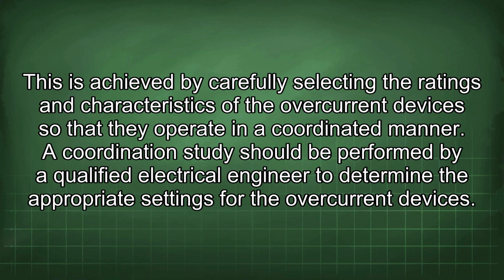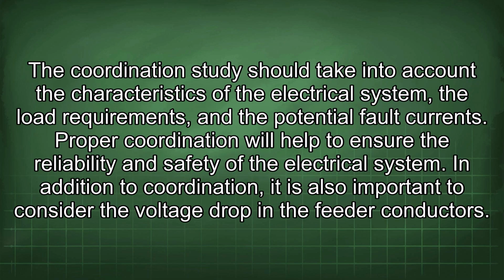This is achieved by carefully selecting the ratings and characteristics of the overcurrent devices so that they operate in a coordinated manner. A coordination study should be performed by a qualified electrical engineer to determine the appropriate settings for the overcurrent devices. The coordination study should take into account the characteristics of the electrical system, the load requirements, and the potential fault currents. Proper coordination will help to ensure the reliability and safety of the electrical system.